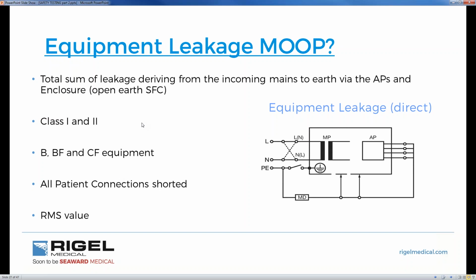So, equipment leakage, means of operator protection. Total sum of leakage deriving from the incoming mains to earth via applied parts and the enclosure. So if we have a look at this diagram over here, this is our medical device, our applied parts, our accessible conductive parts, even isolated parts that might be conductive, are all commoned together here. That's all done within the Rigel. And then we have the facility to open the protective earth. The measuring device, the 1K body model, is within this circuit.